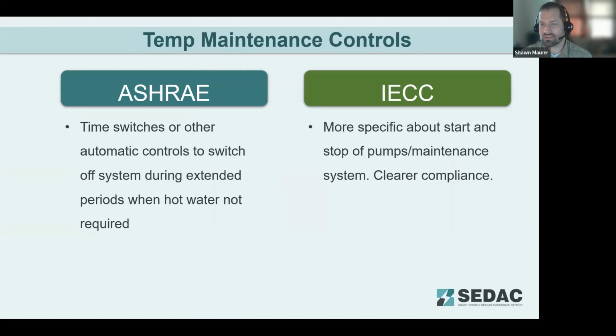For temperature maintenance controls of service hot water systems, both ASHRAE and the IECC have requirements for time switch controls. However, ASHRAE only specifies that time switches or other automatic controls need to turn the system on and off when hot water is not required. The IECC is much more stringent in that it requires an indication of demand in the system to turn the pump on, and then turn it off once the line has reached its set point and has been charged back to temperature. So we've talked about this a lot in the past with the IECC, but ASHRAE does have a more relaxed requirement here, in that time switches are allowed for compliance, where you could set up a building with a regular usage schedule, cycle the hot water when the building's occupied, and turn that off overnight when no one is in the facility.